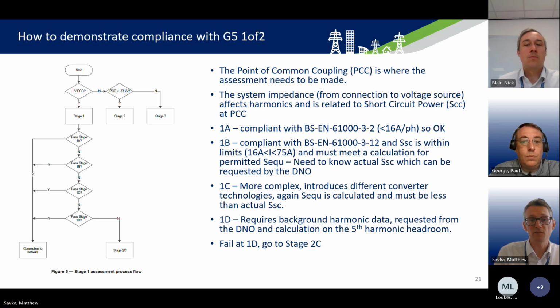For the next stage, stage 1B, is the equipment compliant with BS EN 61000-3-12, and is the short circuit power within limits? So this is for equipment between 16 amps and 75 amps per phase, and it must meet a calculation for the permitted power of the equipment. And to demonstrate compliance with this, you'd need to know the actual short circuit power, and that can be requested from the DNO.